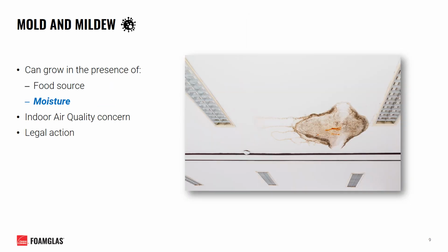Another potential consequence of a failed insulation system on a chilled water line involves the formation of mold and mildew. Mold and mildew can grow in the presence of a food source as well as moisture. While I will mention that most insulation materials don't inherently provide a food source for mold to grow off of, most of the time the food source is introduced to the system after the fact. That could be something as simple as dust, debris, nearby floating skin cells, or other byproducts of the natural environment. Once moisture is introduced to the system, then you're at risk for the formation of mold and mildew to grow, posing an immediate indoor air quality concern for those around.